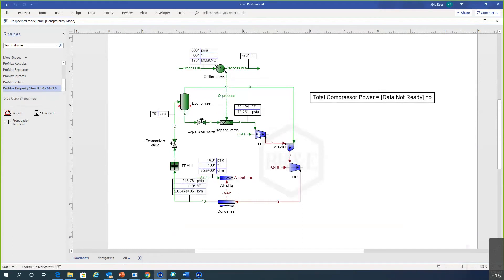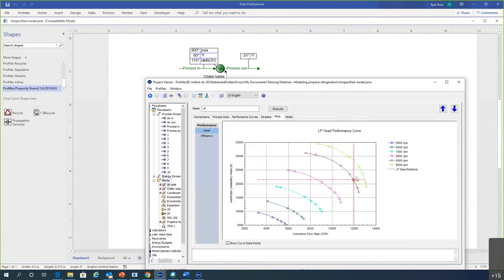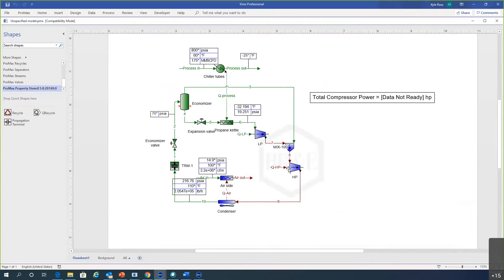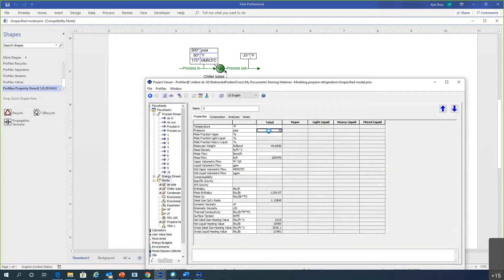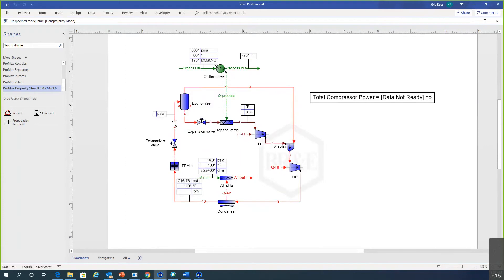We'll set the HP compressor speed to 9,000 rpm — looking at the plot that puts us on the performance curve. With these two compressors at fixed speeds, the system will determine the economizer intermediate pressure. Instead of fixing that pressure manually, we add a solver on the economizer pressure to force stream seven's pressure equal to stream three's pressure.